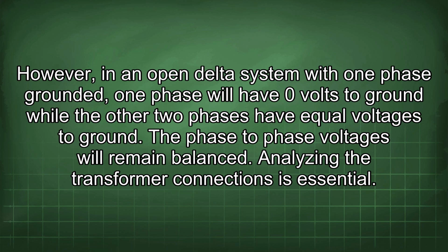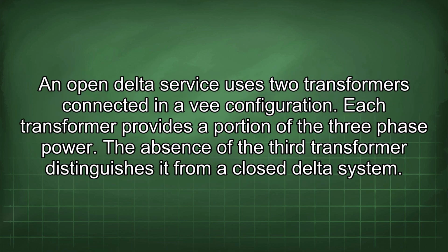Analyzing the transformer connections is essential. An open delta service uses two transformers connected in a V configuration. Each transformer provides a portion of the three-phase power. The absence of the third transformer distinguishes it from a closed delta system.